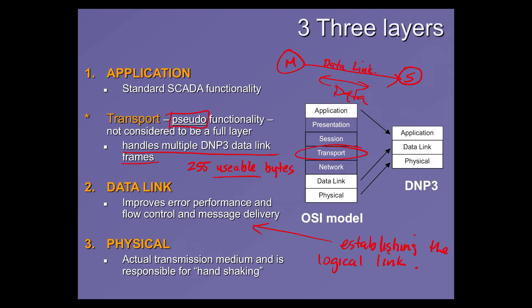If you have a master and a slave in DNP3, the data link layer builds that bridge by which you can move data back and forth between the two, establishing that on a session basis. Every time the master comes around to talking to that slave, it uses the data link layer to establish the logical link, then moves data over that logical link. Sometimes DNP3 messages are just a data link layer message only — like a ping to confirm the logical link is still established and check connectivity. The physical layer can be RS-232, RS-485, or Ethernet.